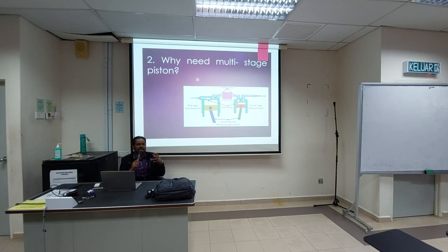Jangan application you perlukan 10 bar, you tiba-tiba pergi install multi-stage. Tiba-tiba you supply 250 bar. Kemudian you perlu ada pressure regulating valve untuk kurangkan balik ke 10 bar. So janganlah. One thing is expensive. Another thing is defeat the purpose. Kenapa you tiba-tiba perlu increase ke 250 kemudian kurangkan balik ke 10? So instead you boleh gunakan single stage compressor.